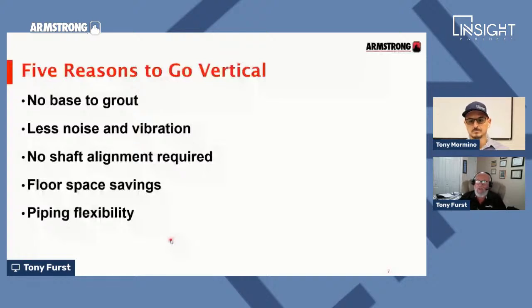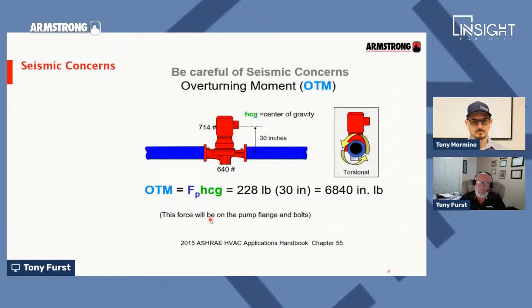The way we deal with that is we can put stanchions underneath the flanges to spread that torsional load out over the floor. Several noise, vibration, and seismic companies make specific torsion or pipe stanchions that bolt to the pipe flanges and to the floor, spreading that load out over a much wider area to eliminate and mitigate the overturning moment forces that happen. You can see the formula.